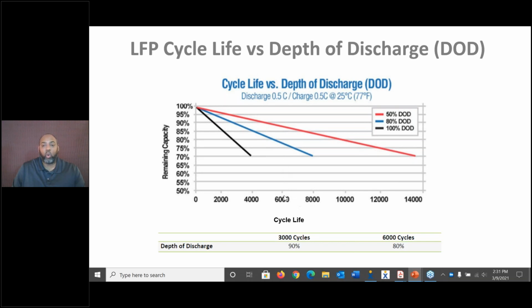Some people do warrant the battery for 10,000 cycles, but that's really not realistic in terms of being able to achieve it. Not saying it can't happen, but realistically at 80% depth of discharge, this chart shows you'll be able to get to 6,000 cycles, and that's why we warrant our batteries for 6,000 cycles at 80% depth of discharge.